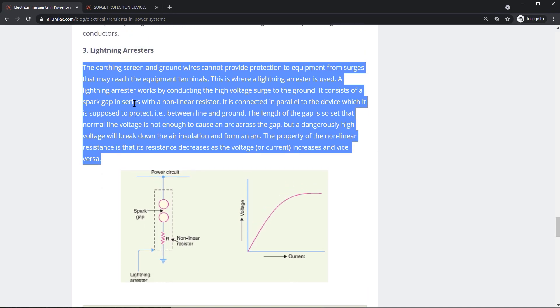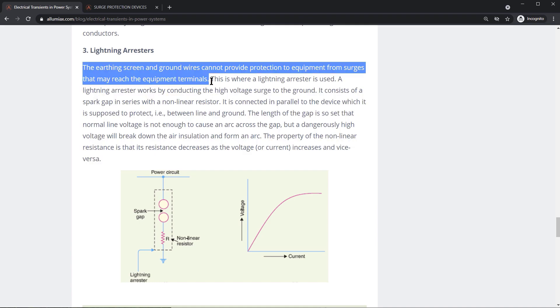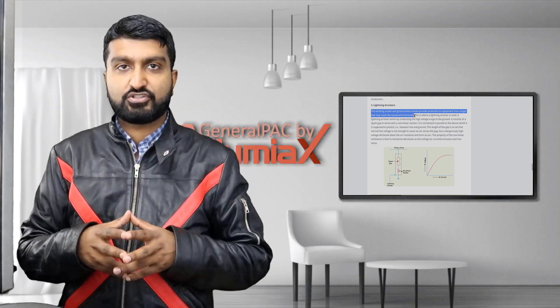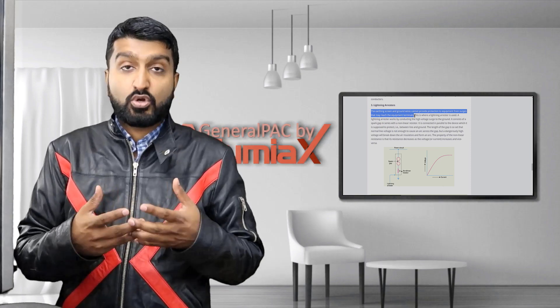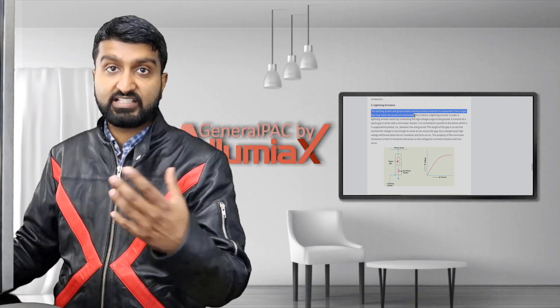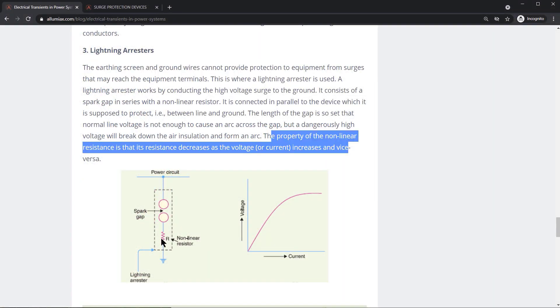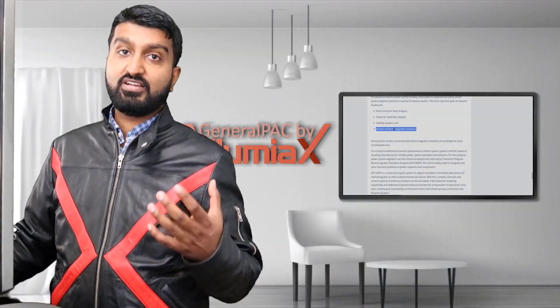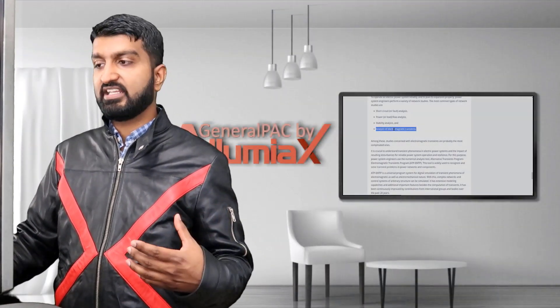Lightning is more likely to strike the overhead ground wire first since it is the furthest point from ground. Lightning arrestors are a very common installation used on the utility grid as well as on transformers. Overhead ground wires cannot protect equipment at the bushing level, but lightning arrestors can because they are installed in close proximity. When the voltage increases, the resistance of the arrestor decreases significantly, so the transient arcs across and is directed to ground.